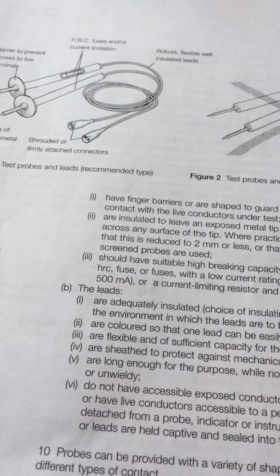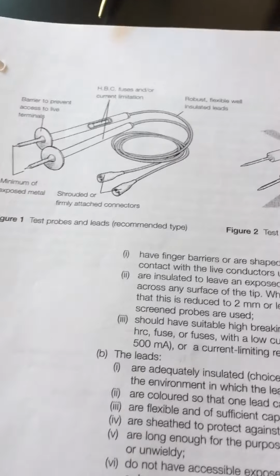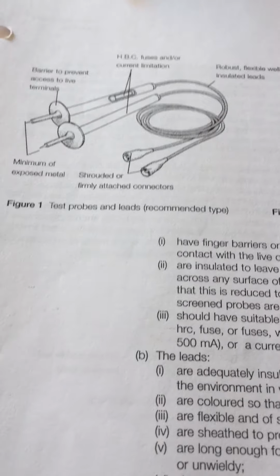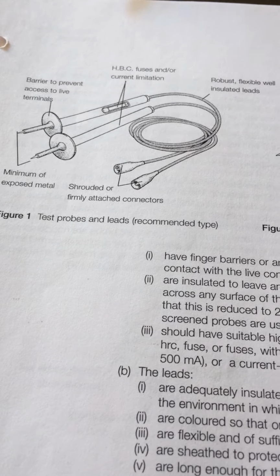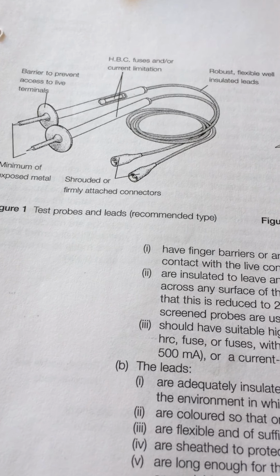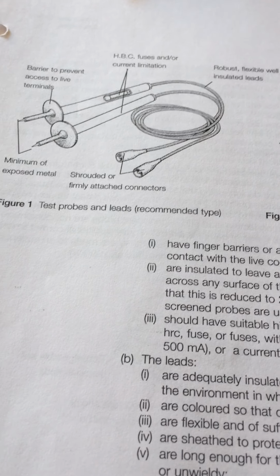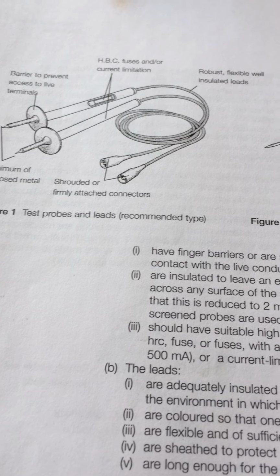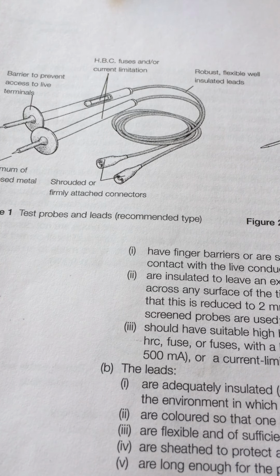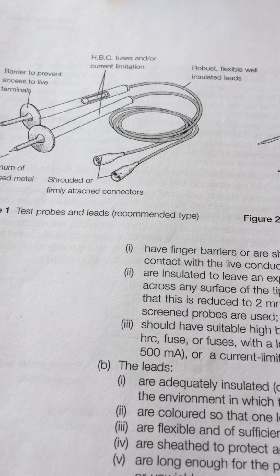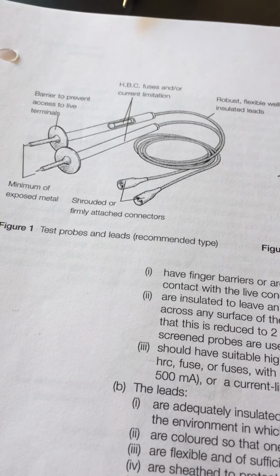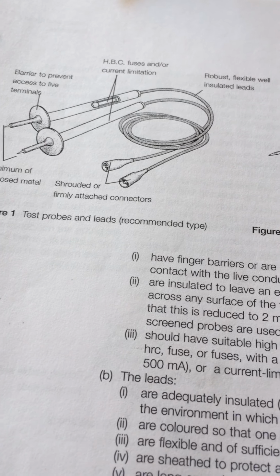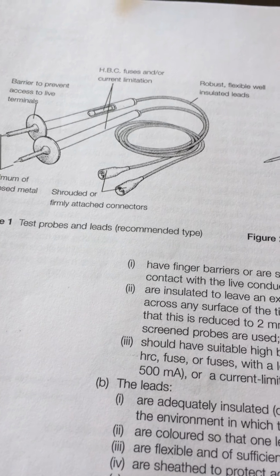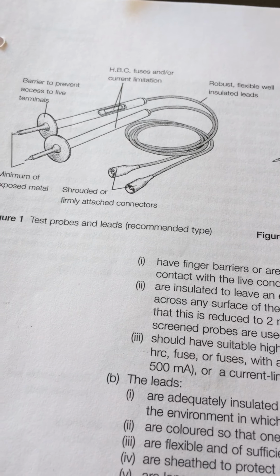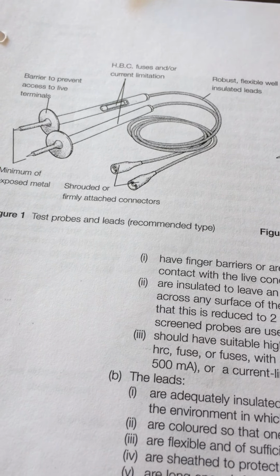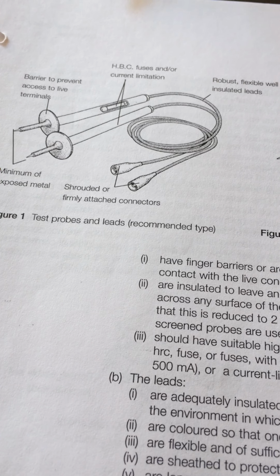It's a health and safety leaflet that was issued by the Health and Safety Executive sometime after 1989, because it mentions the Electricity at Work regulations, which came out in 1989. And the focus of it is the kind of test probes and leads that we should be using for live testing. And it mentions in the document that the particular focus is if we're working on circuits or equipment where the voltage is above 50 volts AC or 120 volts DC, then we really need to be thinking about using GS38 approved leads.